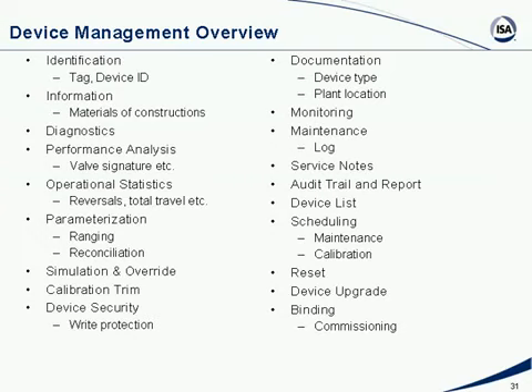I can do configuration or parameterization of the device. I can change the range. I can reconcile the configuration of the device against my database, to see that when I connect a new device, I can make sure that it's properly configured. I can do simulation and override. I can essentially make a loop test with a Fieldbus device. I can simulate a high pressure or a high temperature to make sure that all my interlocks are working okay. Calibration trim, to correct for drift, is possible. I can check on device security, if the right protection is on in my devices, etc.